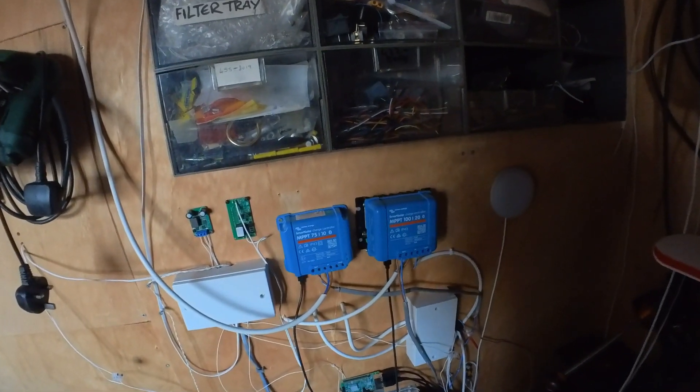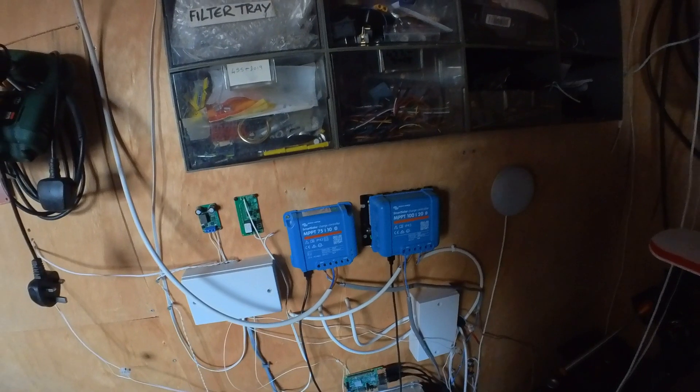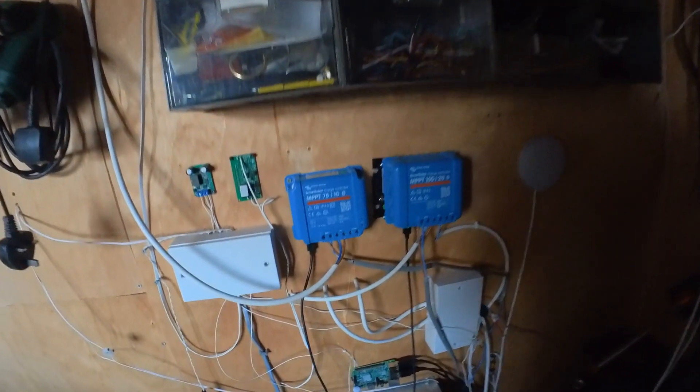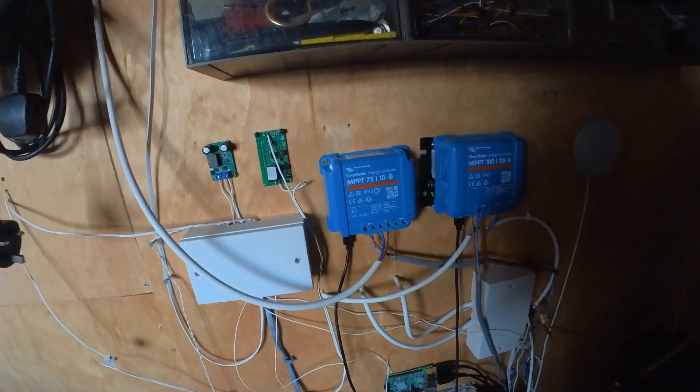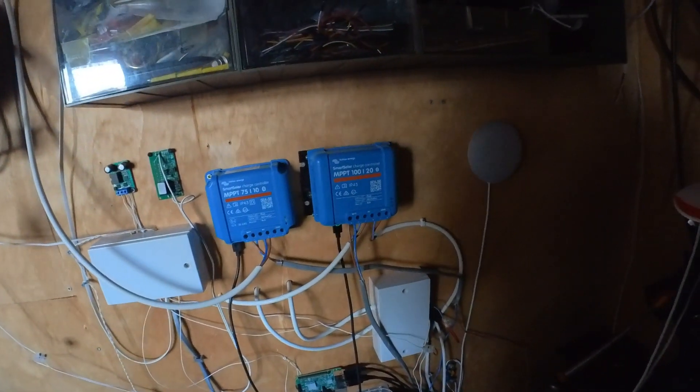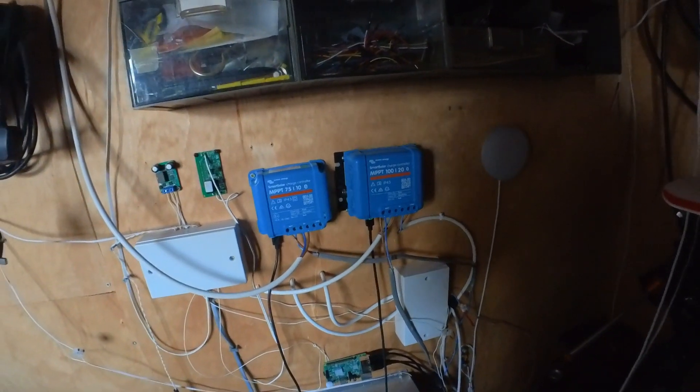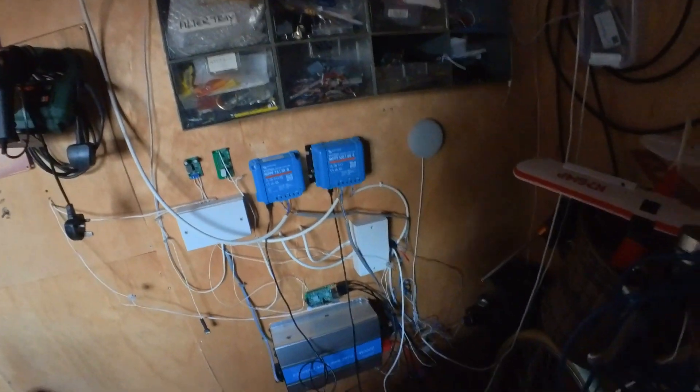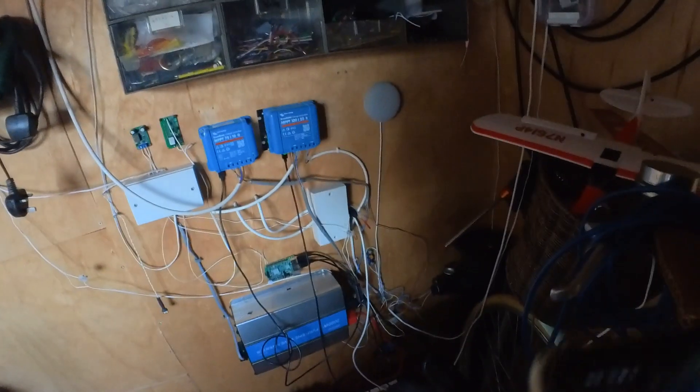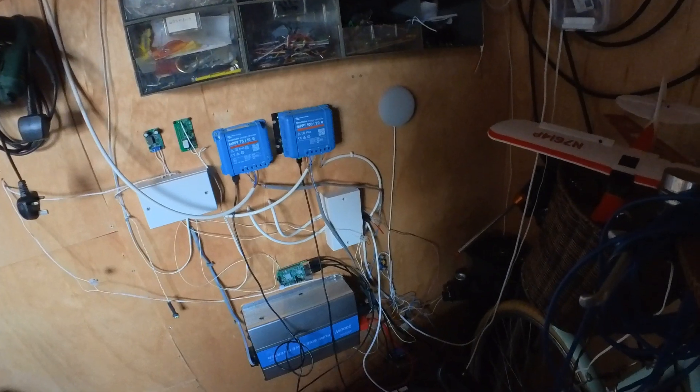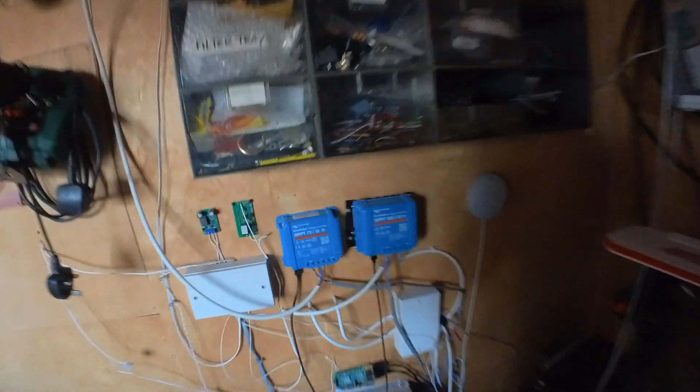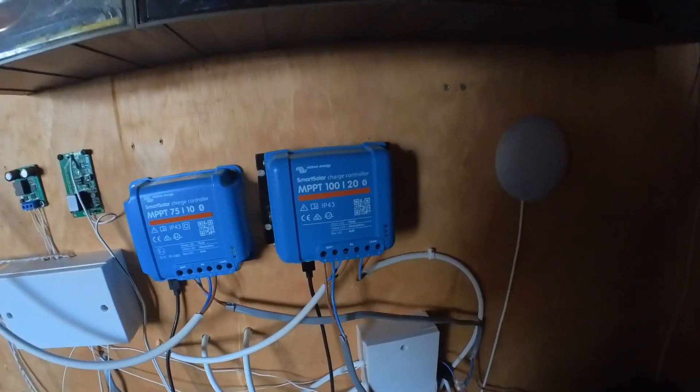But because these Victron charge controllers can charge a dead battery, these are powering themselves from the actual solar. So even though there is no solar power, they're still on and there's no power from the battery. That's how come we can still connect to them and still see them here—they're getting a small amount of power from the solar.